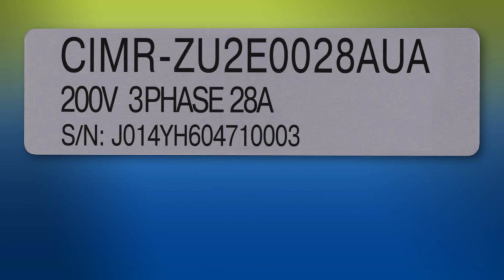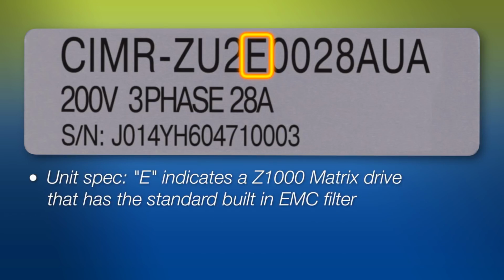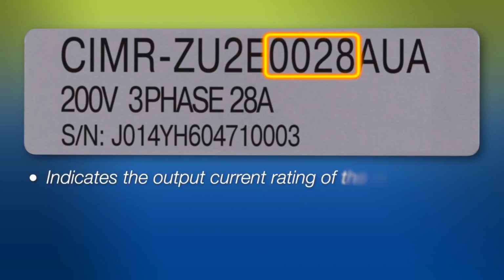The next designator determines the unit's spec. The letter E indicates a Z1000 matrix drive that has the standard built-in EMC filter. The 4-digit number indicates the output current rating of the model, in this case 28 amps. This will be key when we discuss unit selection.